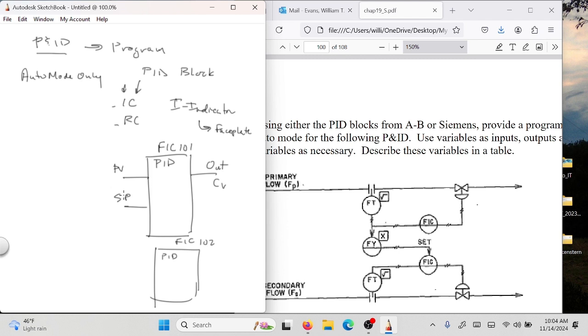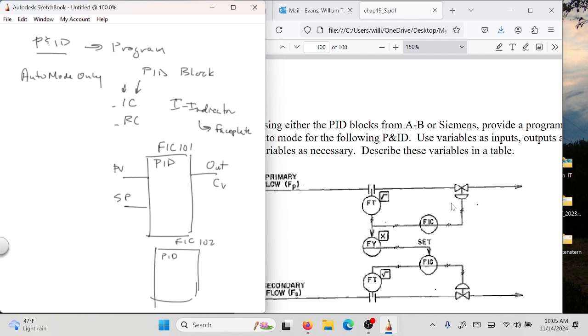We're trying to fill in two inputs and one output for these PIDs. In this case, we have an FT that goes to an FIC — the arrow shows the direction. A valve is an output device — it's something that's controlling something, and the signal coming from the FIC is the output. Those dashed lines can mean either electrical or pneumatic signal. I'm going to control it with an electrical signal — either 0 to 10 volts or 4 to 20 milliamps.